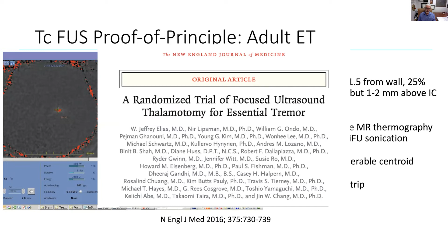So how does this thing work? Well, the way it works is that it uses a transducer system that has 1,000 plus piezoelectric transducers. They convert electrical energy to sound waves. They're situated in a dome, and that dome is built into this helmet. The dome focuses all of the energy on a single point. And that single point has a very sharp peak with a very brisk drop off.